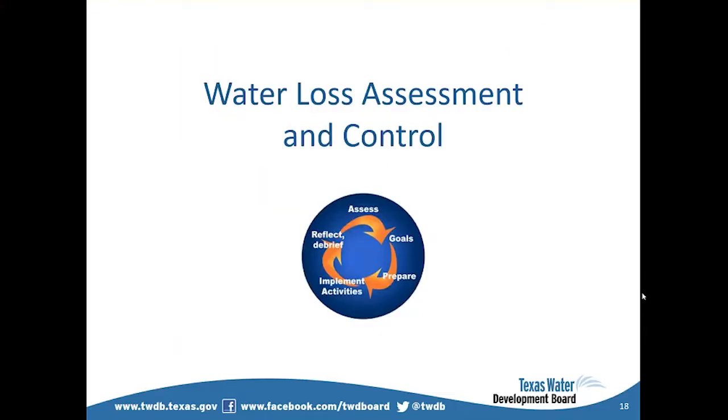All right, so at this point, if you were filling out an audit, you would have completed everything on there except for one thing, and that is the assessment scale. Now, the assessment scale is basically asking the utility what the conditions are at the system that provided the data that they input into the audit. So there are 20 fields on the water loss audit which are asking for an assessment scale, and that scale is 0.5 to 5, and there's actually an assessment scale table which helps the utility identify what number they need to choose for that assessment.